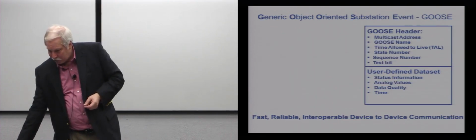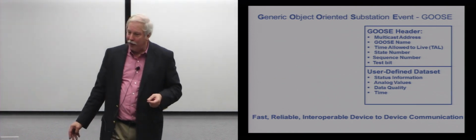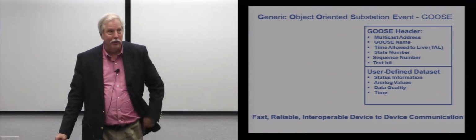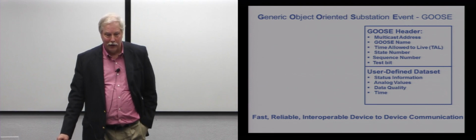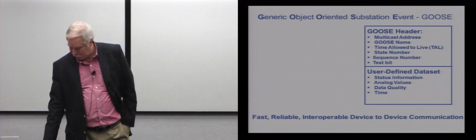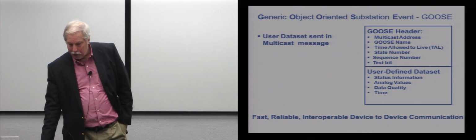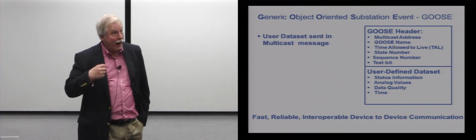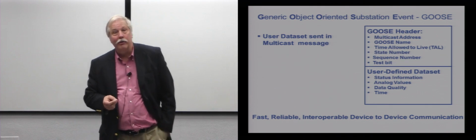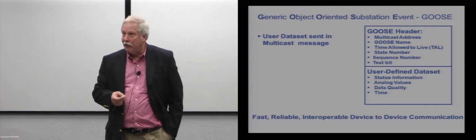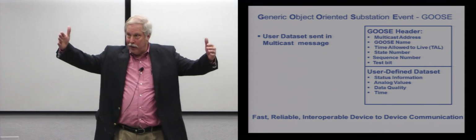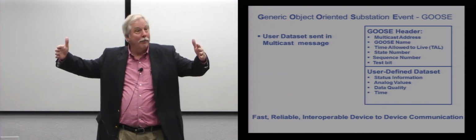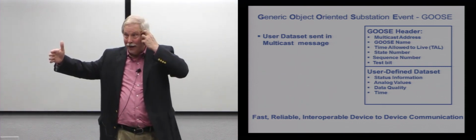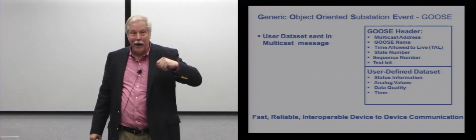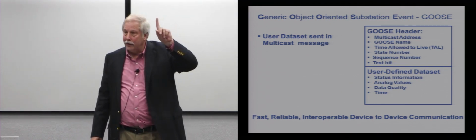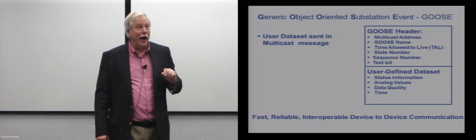The name for this is the Generic Object-Oriented Substation Event, or GOOSE. The GOOSE is a publisher-subscriber message. It's a multicast - multicast is a special feature of Ethernet. It turns out an Ethernet address has 48 bits in the address space, and if bit 8 of that address is set to 1, it identifies that message as a multicast message.